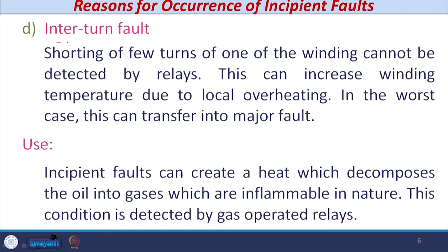The fourth reason for incipient faults is interturn faults. Whenever a few turns of one phase or multiple phases are shorted together, there are fair chances of temperature increase due to local heating. In the worst case, this may transfer into a major fault. Keep in mind that interturn faults occur in a particular phase or multiple phases. The differential protection normally used is not capable of detecting such interturn or turn-to-turn faults, so we need to detect this with a separate device or arrangement.